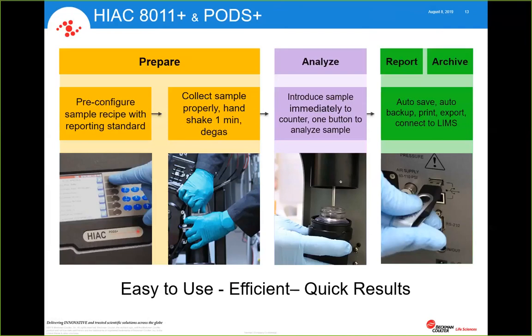You take your sample, you make sure you draw from the correct position on your system, you agitate it to get those particles in suspension. You then do a degas function to get the air out, because air in particle counters actually shows up as particles because it blocks light through the laser. So preparing the sample properly, you agitate it, you degas it, and then you quickly run it. You do not want any time to go by between those 3 steps.